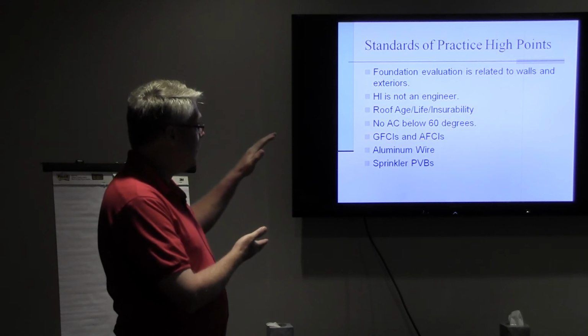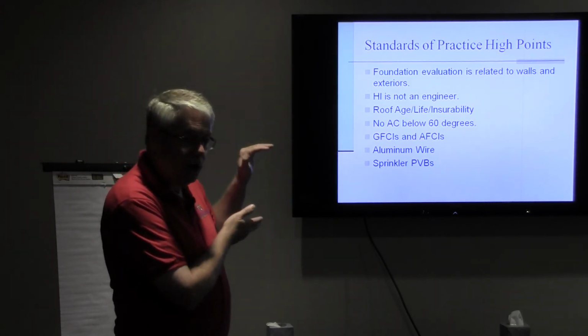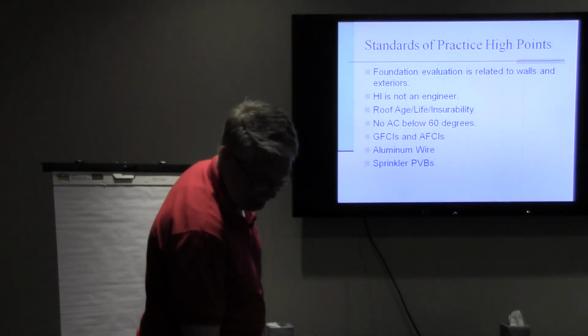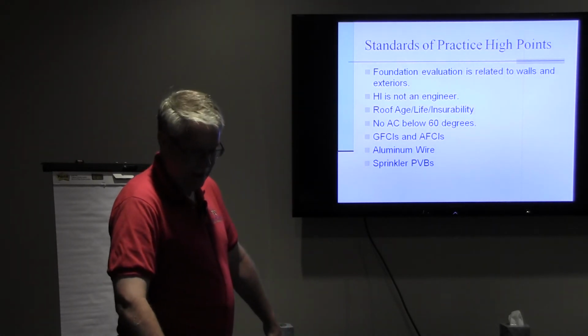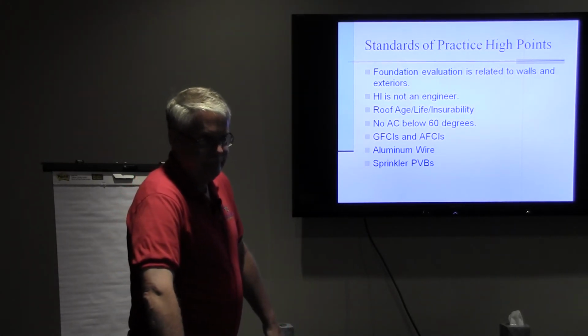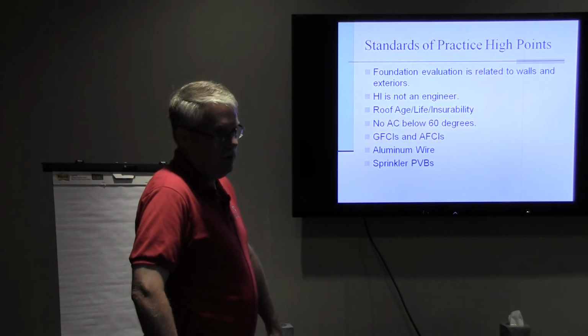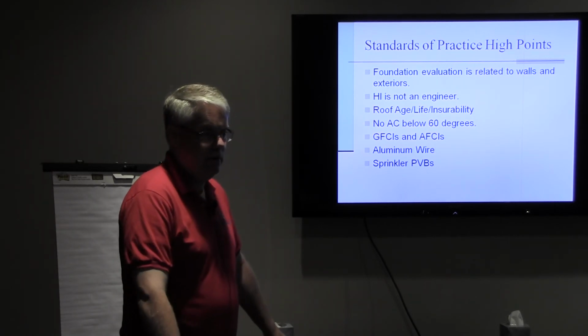So there's a great example of something I have to tell your client, and then I say, I would not do it. You just gave me an aha moment, because my house is 2 years old and my builder's warranty hadn't come out, because I could plug my vacuum in and it was a low breaker every time. It's so frustrating. It's probably that that's doing it. It's either a bad arc fault, or there's too many outlets on the circuit, or it's a 15 amp circuit instead of a 20. I think it was a bad arc fault, so they came in and did something in my breaker box and changed it out.